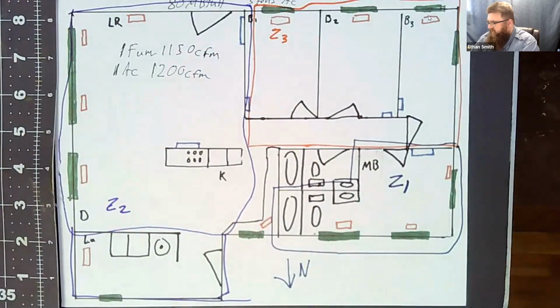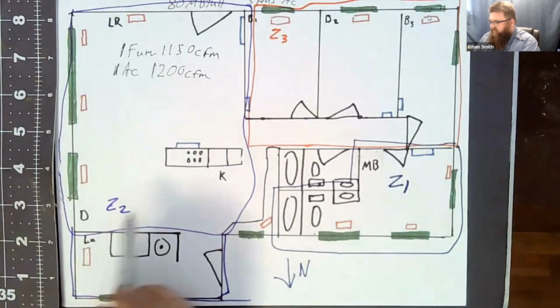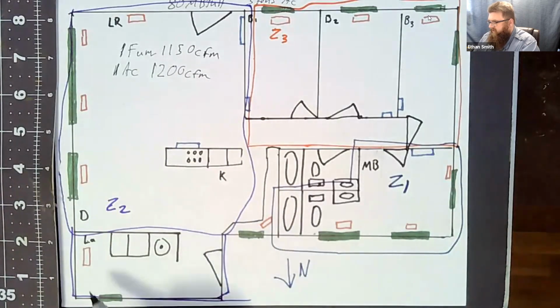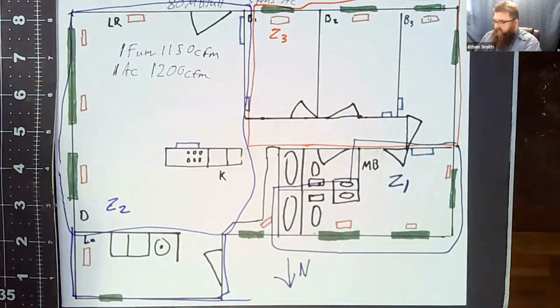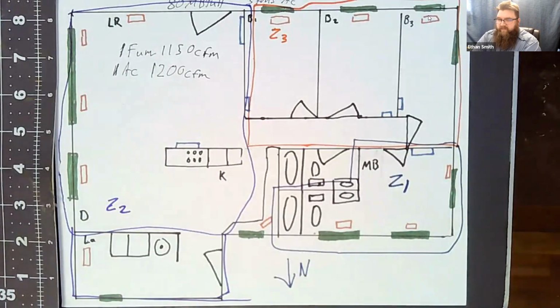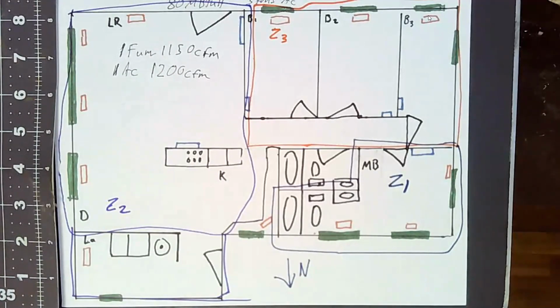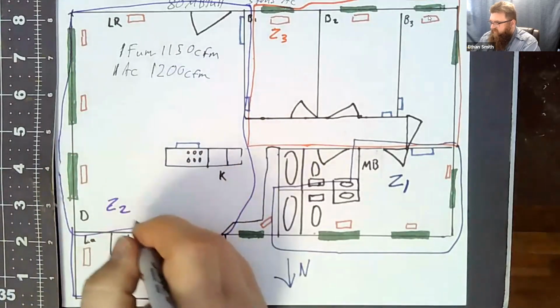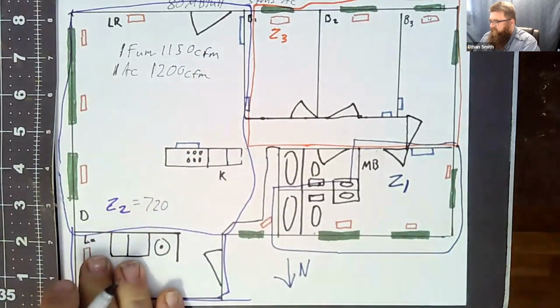Okay. So these being single stage units, can I close a zone on this thing and still have it work? And here's my biggest zone. This is my zone 2, this living room, kitchen, dining room, laundry room thing. I've got 1, 2, 3, 4, 5 runs there. Oh, 6. I picked up one in the kitchen here. So I've got 6 runs at 120 CFM apiece. How many CFM can I push in that zone? 720. It's around 720. Yep, right around 720. So zone 2 is equal to 720 CFM. Zone 3, 300.